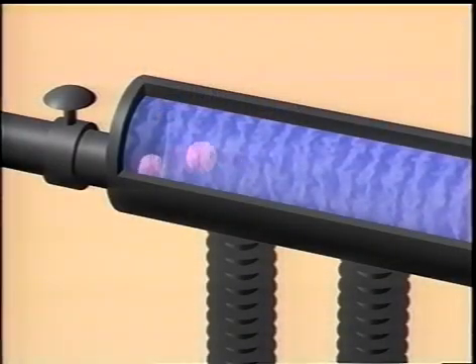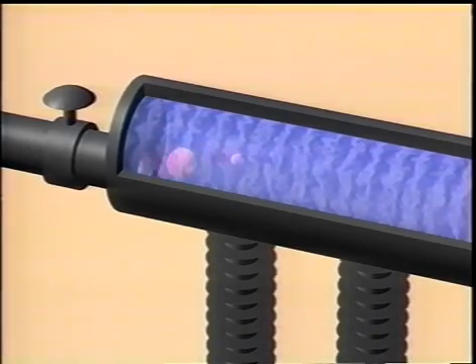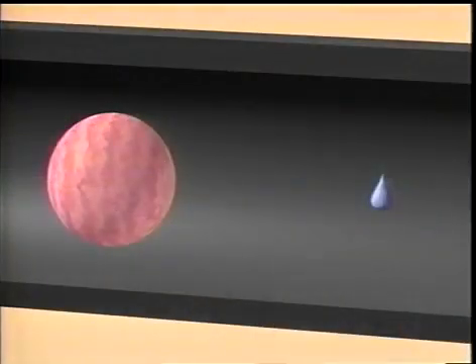Water hammer may also be initiated by thermal shock. In biphase systems, steam bubbles may become trapped in pools of condensate. Since the condensate temperature is usually below saturation, the steam will immediately collapse. Steam occupies hundreds of times the volume of an equal amount of water. When the steam collapses, water is accelerated into the resulting vacuum from all directions. When the void is filled, the water impacts at the center, sending shock waves in all directions.